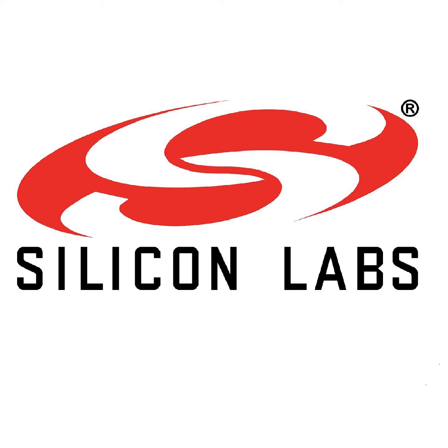Yeah, well, and it all comes back to what I said about this nasty environment. All those challenges culminate in some key things you've got to do in the design. The first one is tolerating overloads. Because we don't know what's attached to the channel, it's very easy for that to be an overloaded actuator. It could be something too large, or you could have somebody miswire it and attach your output to a dead short. 24 volts into ground can sink a ton of power and blow things up.